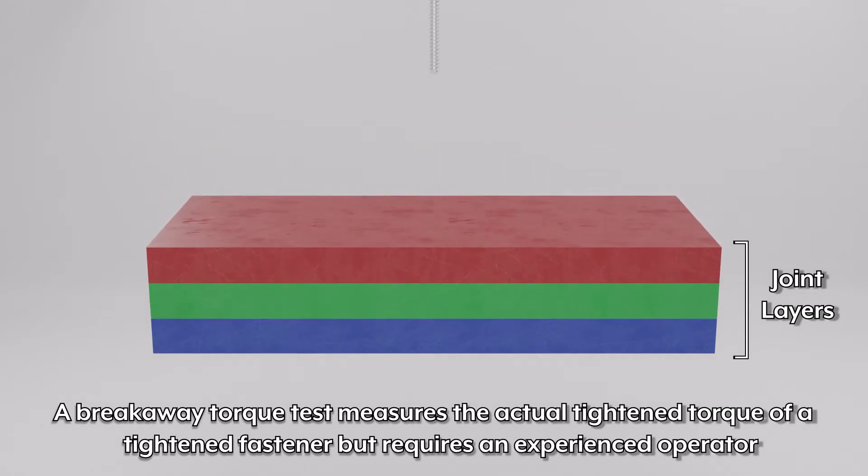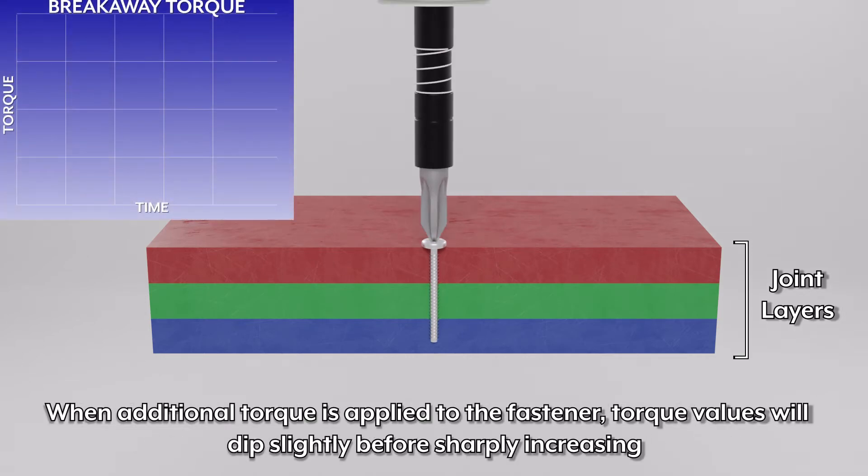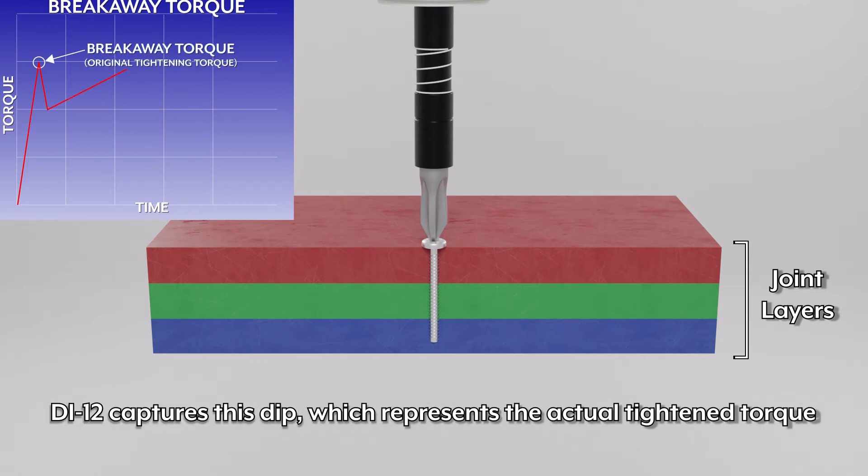A breakaway torque test measures the actual tightened torque of a tightened fastener but requires an experienced operator. When additional torque is applied to the fastener, torque values will dip slightly before sharply increasing. The DI-12 captures this dip which represents the actual tightened torque.